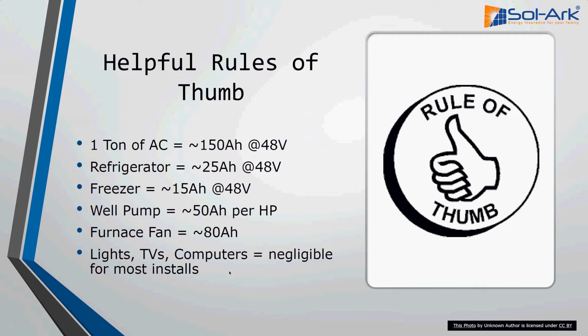When in doubt, if you have a residential application and your customer just wants to know, 'hey, if I only want to back up my critical stuff, I don't want to do the AC, I don't want to do anything like that, I just want to cover my refrigeration, lights, computers, and those kinds of things' - 400 amp hours of carbon AGMs or about 200 amp hours of lithium will be just fine for most applications where they don't want to do the really big stuff off-grid. That's just a good rule of thumb if you have to give a quick off-the-cuff quote to the customer.